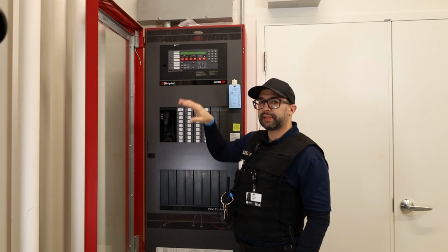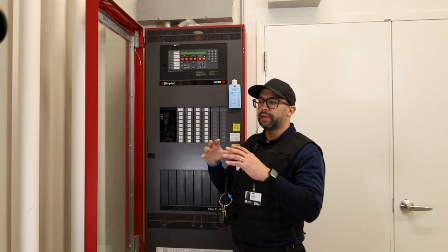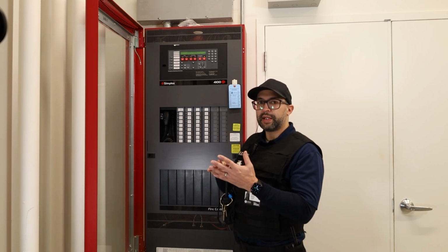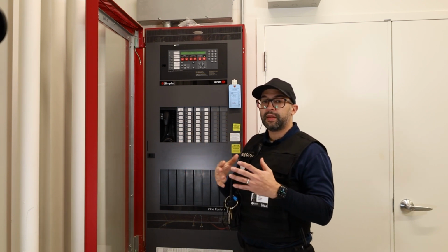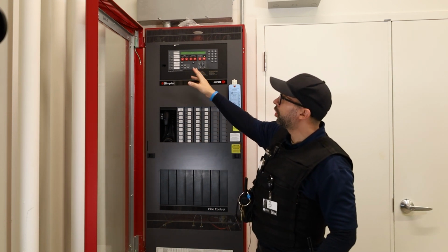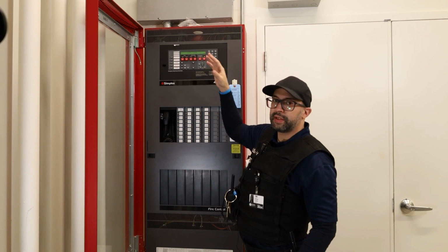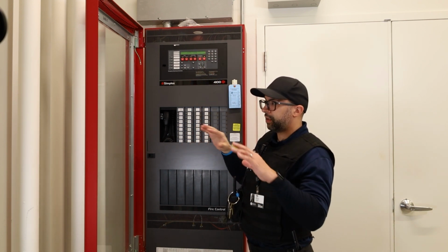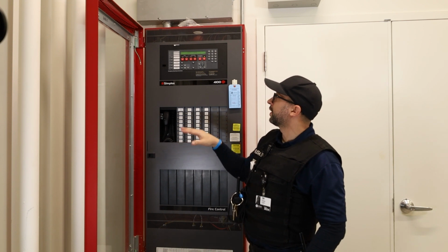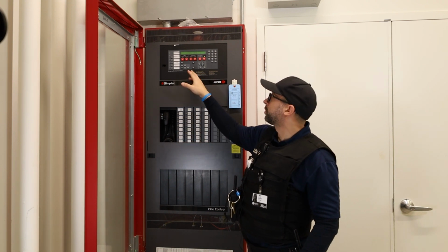And then this is the alarm silence key. What that key does is, once you've discovered the fire or the device that was initiated, and you observe that there is no real fire, you come down here and you can silence the alarm, and that way everything goes back to silent, and there are no more horns and strobes going off. System reset has to do with if there is a fire and you clear it, and we'll talk about clearing fires later on. Basically, you would just come to system reset, and that'll reset the system.